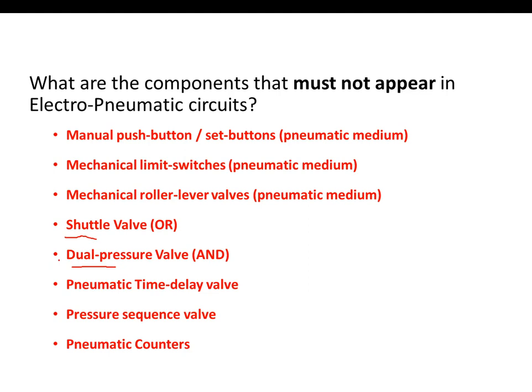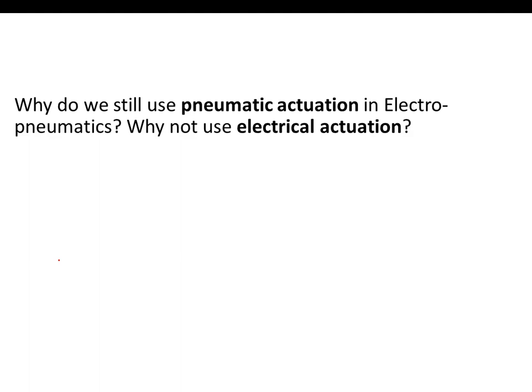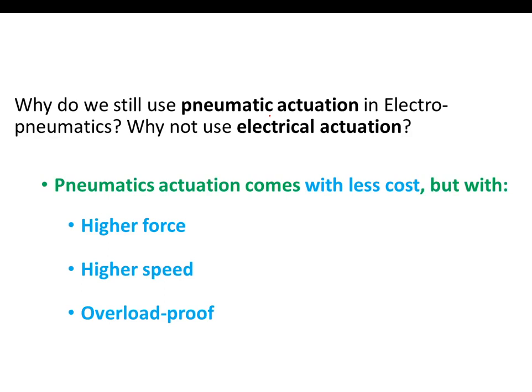Why do we still use pneumatic actuation? This is a question always posed by viewers — why not replace pneumatic actuators with electric motors? The reason is that pneumatic actuation costs less, brings higher force, higher speed, and it is overload proof. Overload proof simply means when you overload the pneumatic motor, it will not spoil.